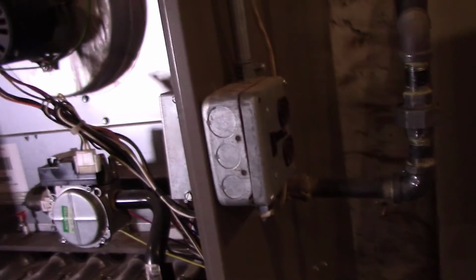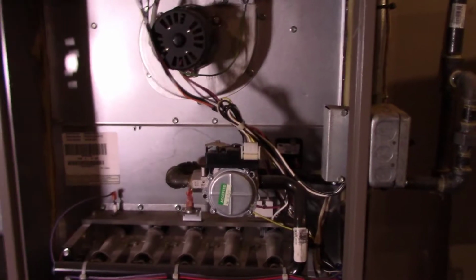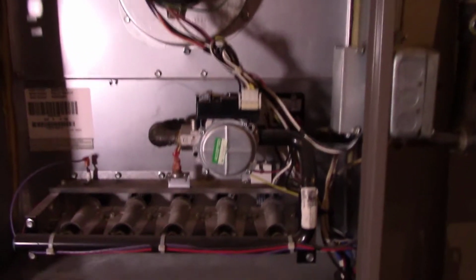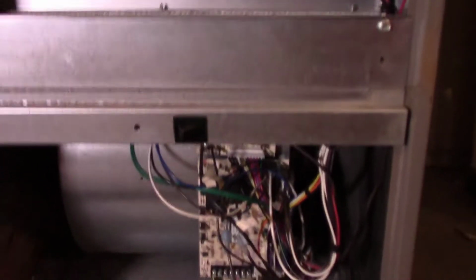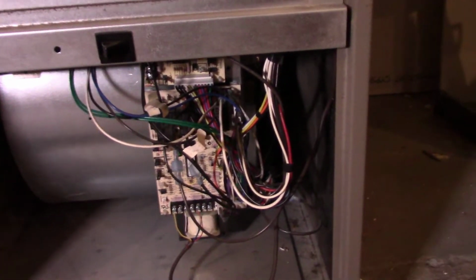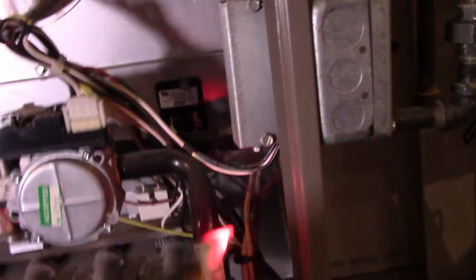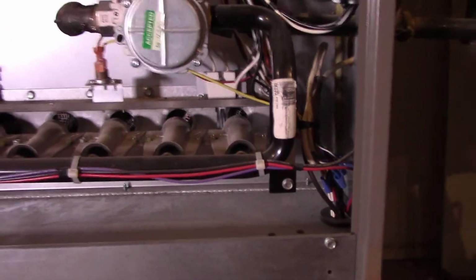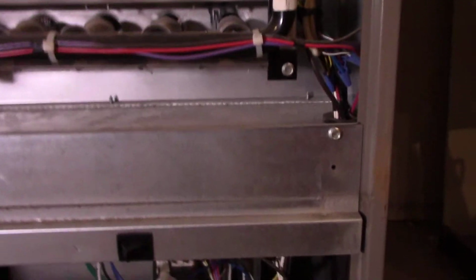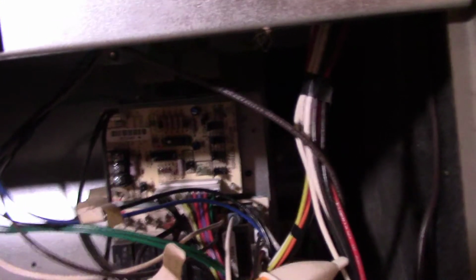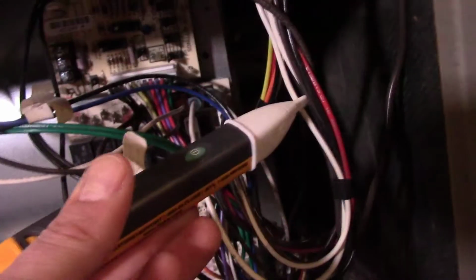Okay, so now that we know there's power coming into the furnace, let's look a little bit further. Most furnaces have what's called a main board or a control board, usually at the bottom by the blower motor if you're in an upright furnace like mine. We know that we have power coming in, but yet the furnace still isn't running. So one of the things we can do is trace down the wires that come down to the main board. We should have a wire going into the board. One of these black wires should have power to it.